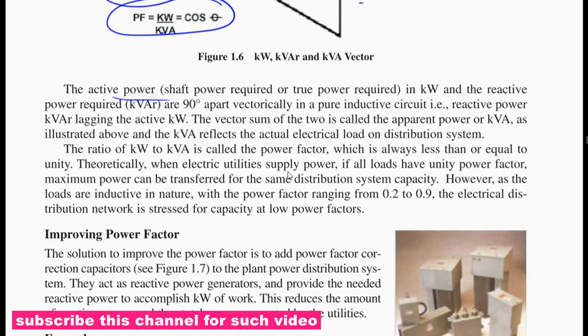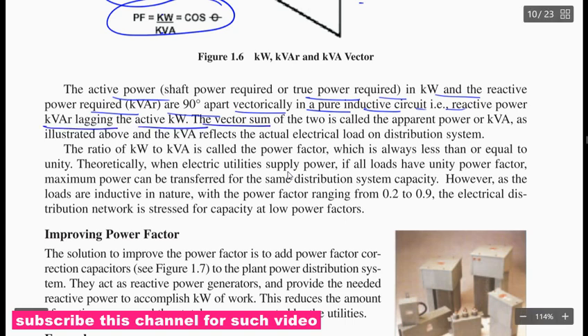The active power, shaft power required or true power required in kilowatt, and the reactive power required are 90 degrees apart vectorically in a pure inductive circuit, and reactive power kVAr lags the active power kilowatt. The vector sum of the two is called apparent power in kVA, as illustrated in the example. And kVA reflects the actual electricity load on the distribution system. The ratio of kilowatt and kVA is called the power factor, which is always less than or equal to unity.